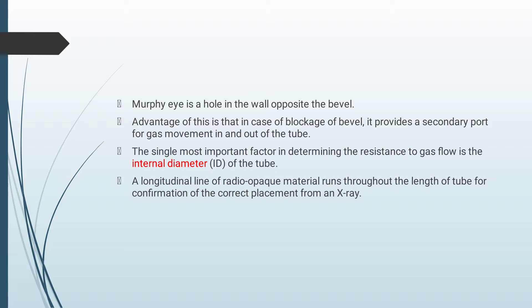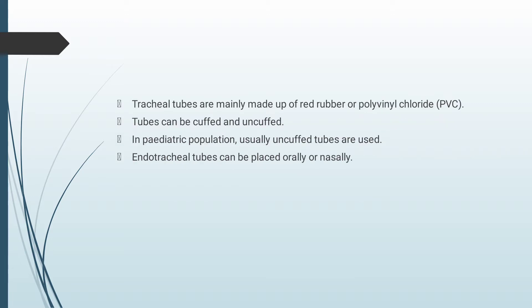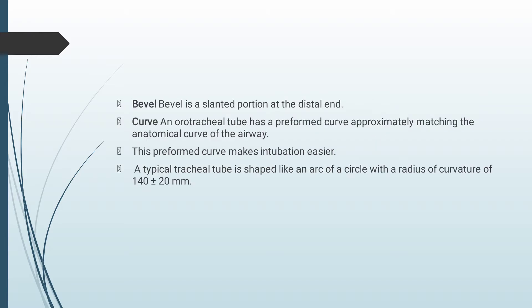Murphy's eye is a hole in the wall opposite the bevel. In case of blockage of the bevel end, it provides a secondary port for gas movement in and out of the tube. The single most important factor in determining resistance to gas flow is the internal diameter of the tube. A longitudinal line of radiopaque material runs through the length of the tube for confirmation of correct placement on X-ray. Tracheal tubes are mainly made up of red rubber or polyvinyl chloride and can be cuffed or uncuffed. In the pediatric population, usually uncuffed tubes are used. Endotracheal tubes can be placed orally or nasally. The bevel is a slanted portion at the distal end. An orotracheal tube has a preformed curve approximately matching the anatomical curve of the airway, making intubation easier.